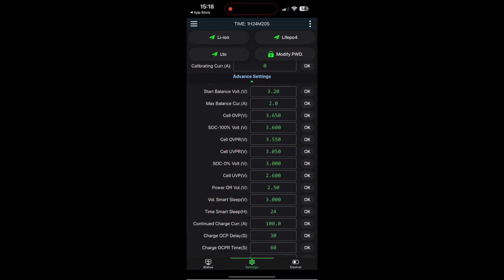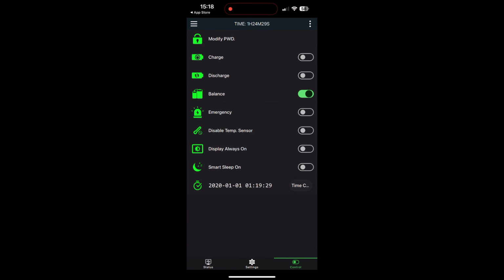I can see here there's a couple of settings that haven't been set up, so I'm going to change that to 3 volts. Okay, control. In the controls you can set up what you want. So for example, this charge basically means, do you want charge to be able to go into the bank? Same with discharge. Do you want the BMS to allow discharge to come out of the bank? Balance, self-explanatory in my opinion. Basically, do you want the BMS to be balancing your cells? We can turn that on and off, okay?